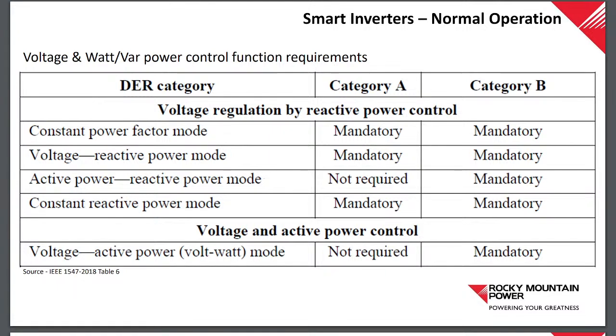The category is just a setting. Category A makes mandatory the constant power factor mode, the volt-var mode, and the constant reactive power mode. B widens the capabilities of that inverter for regulation - it's all of category A, plus it allows for active power, reactive power mode, as well as volt active power mode, which is volt-watt. You'll hear volt-watt or volt-var a lot. Volt-var is where a lot of utilities, and it seems pretty industry-wide, are settling, so that's kind of where we're going with category A versus category B.